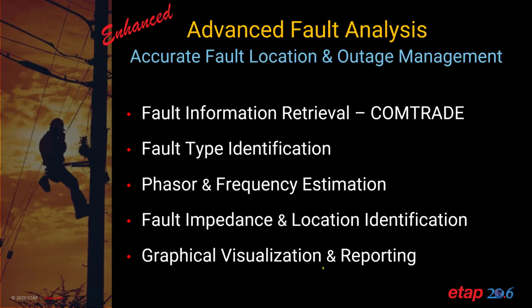Advanced fault location allows us to retrieve information in a COMTRADE format and perform fault identification through various phasor and frequency estimations. The AFAS module has been enhanced in terms of its graphical visualization capability, and it now allows us to compare the as designed versus as operated sequence of operation in the same interface.